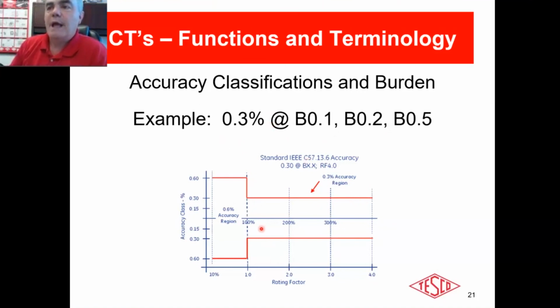Remember, if this is a 400 to 5, it doesn't reach 0.3% until you are at that 400 amps. If it has a thermal rating factor of 4.0, it's going to maintain that accuracy all the way out to 1600 amps, or 4 times its rating. If this was a 200 amp to 5, 200 amps would be right here. It would be accurate at 200 amps all the way out to 800 amps. All right, everybody got that?